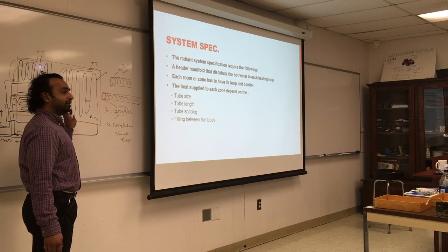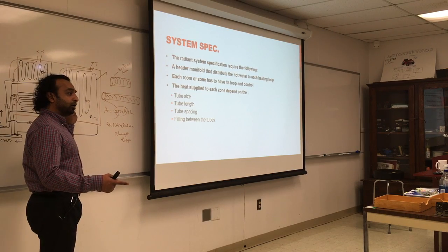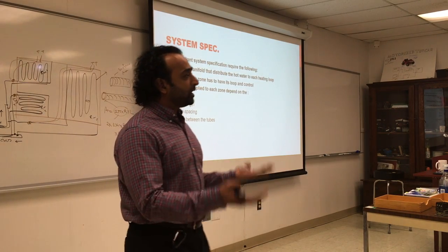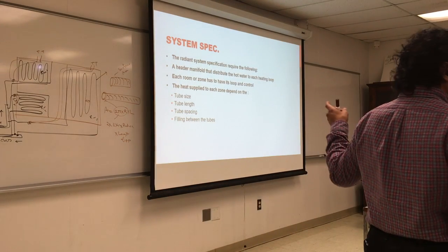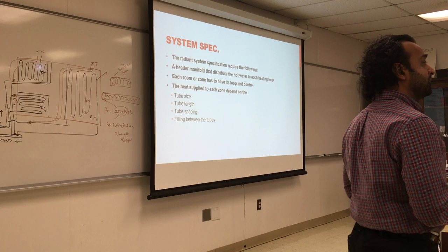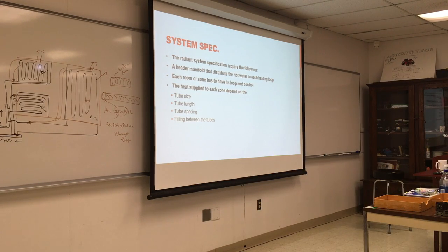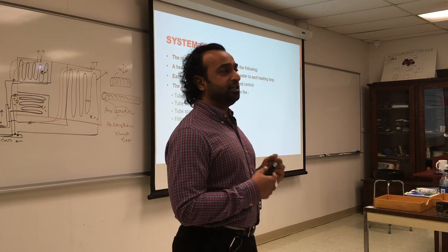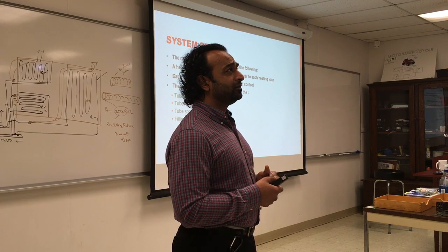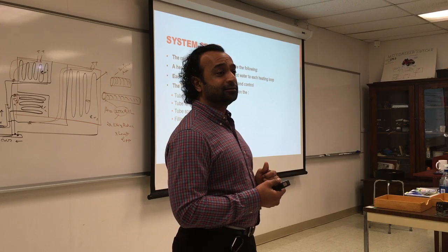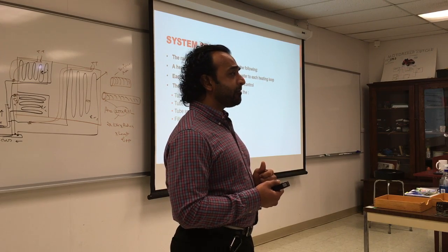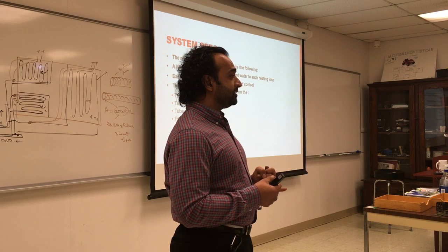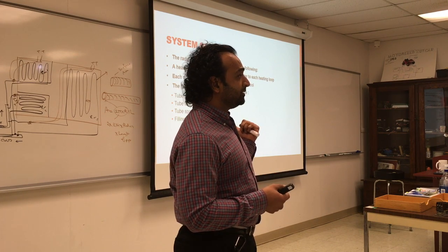You have to really have the right amount of velocity going to the water. And again, there's a lot that goes into what is the heat coming out of it. But the spacing and the tube sizing is fixed to have a velocity maximum of 3 feet per second. If you have more heat, you can have the water go faster or slower. There's a lot to manipulate to get the heat up and down. But what happens if it goes too fast? We don't want to exceed 3 feet per second, which is around 1 meter per second. Would it be noisier? Noisier, more cavitation, and again, you might not drop as much heat as you want.